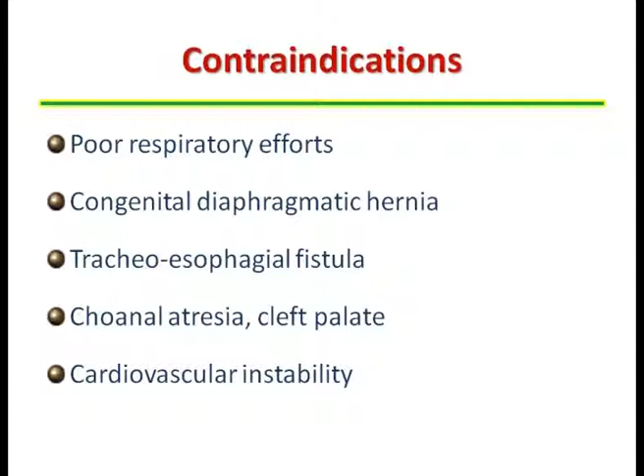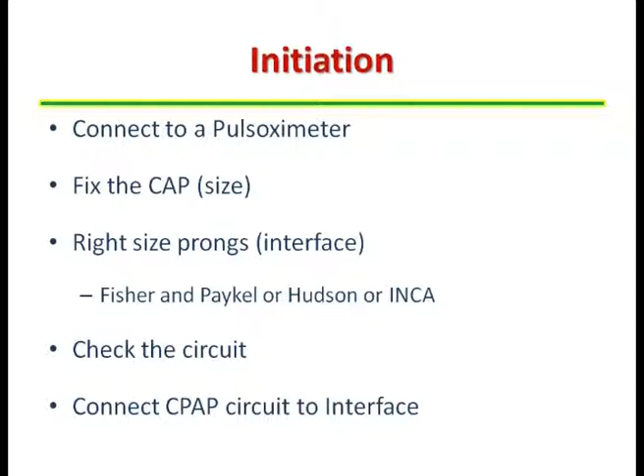Now, when we decide to give CPAP for a baby, the baby needs to be connected to a pulse oximeter, fix the appropriate size cap for the baby, ensure that the cap is covering the ears of the baby, and then choose an appropriate interface. An interface could be a Fisher and Paykel interface, a Hudson prong or an Inca prong, or it can be an Argyle prong. Once you fix the cap and fix the interface, connect the interface to the circuit. Check for leaks in the circuit, which are predominantly at the level of the humidifier and at the level of fixing from circuit to interface.